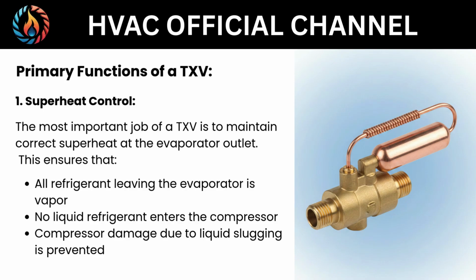Primary functions of a TXV. 1. Superheat control. The most important job of a TXV is to maintain correct superheat at the evaporator outlet. This ensures that all refrigerant leaving the evaporator is vapor. No liquid refrigerant enters the compressor. Compressor damage due to liquid slugging is prevented.